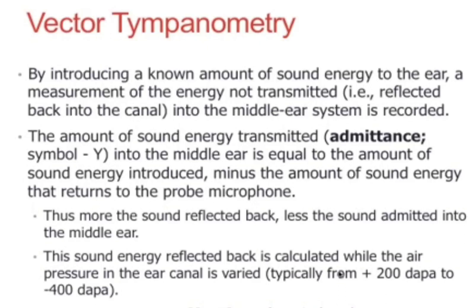In tympanometry, what we do is we give some amount of sound energy in the air and see how much sound is going inside — that is admitted — and how much is reflected back. It is not possible to measure what sound is admitted inside, but we can measure what sound is reflected back. So if we know how much sound is reflected back and subtract from the total energy supply, we indirectly get the measure of how much sound is admitted inside.